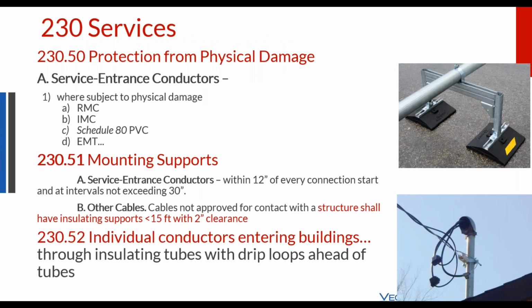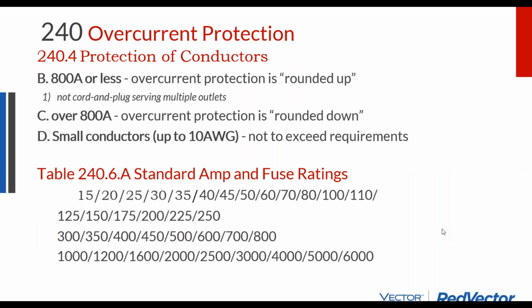Service entrance conductors were subject to physical damage. They say you need to beef up your protection. So this is where it says if your service entrance conductors are subject to physical damage, you need to put them in Schedule 80 PVC or EMT, commonly rigid. Everything's governed by code: the clearance requirements, the distance between supports. Well, here's those drip loops we were talking about.